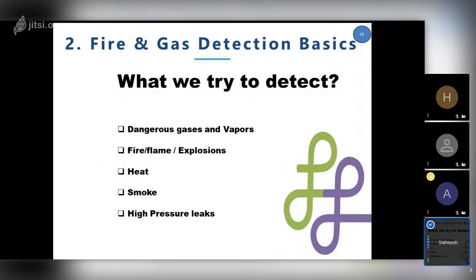The heat detector is normally used in buildings like kitchens and hoods, where you don't know what the temperature increase will be when there is an explosion. So we try to detect with a heat detector if there is a ramp or transient increase in temperature around that area. Smoke is obviously just below fire, and fire is already late. If we get an explosion for some reason, we need to alert immediately and take action to extinguish the flame, keep people away, and keep assets safe.